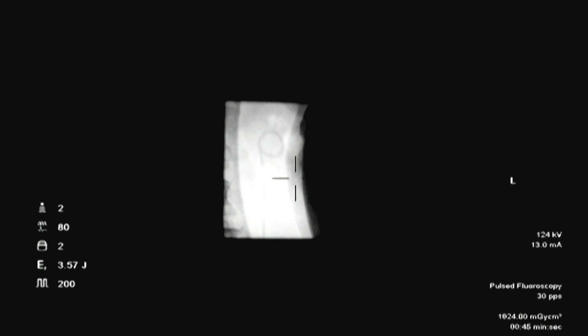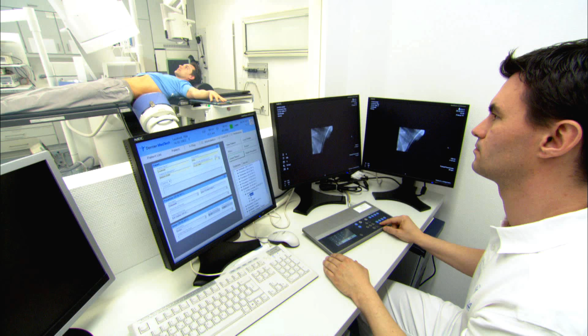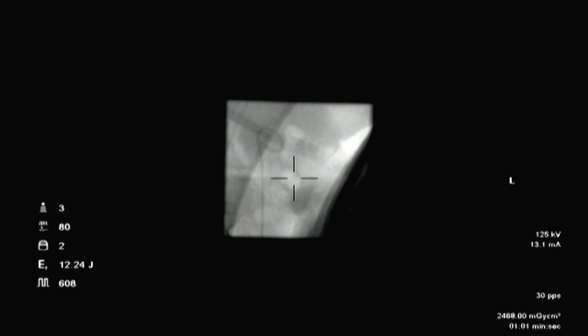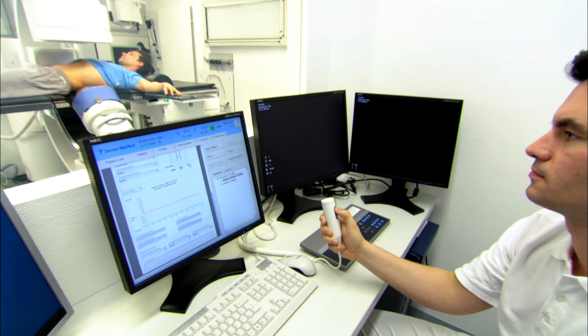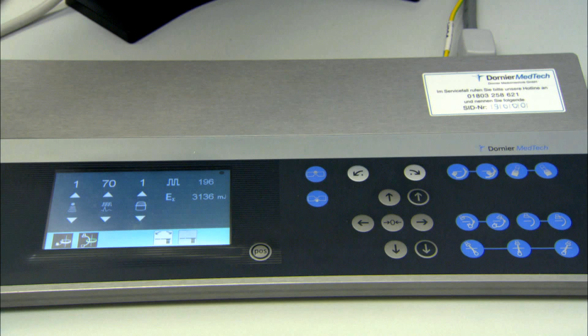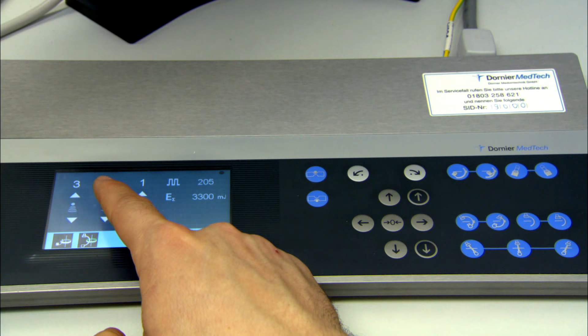After auto-positioning and therapy head coupling, the stone is monitored in the vertical and in the oblique imaging direction. Adjustments are done by simple image-oriented table movements. For radiation dose reduction, collimators are automatically closed to a small field of view. During shockwave release, UIMS continually tracks your treatment parameters and also displays selected parameters graphically on the monitor. Settings for energy level, pulse rate, and coupling pressure are conveniently adjusted by means of a touch screen.